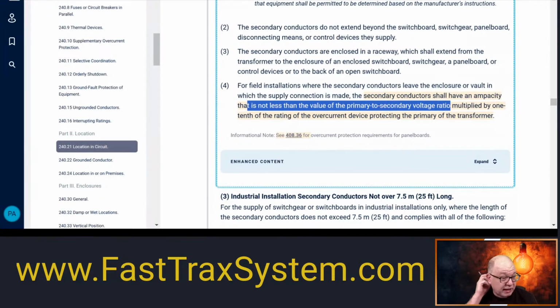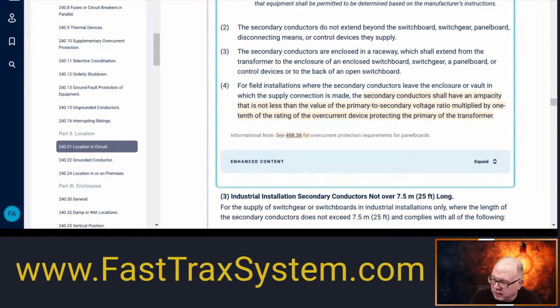And let's say, again, in our case, it was a 480 primary and a 208 secondary. So the voltage ratio would be 480 divided by 208, and that would be 2.307 or 2.31. So that's your ratio. All you did was divide the secondary into the primary to get this ratio. Okay, that's what it means. Then that ratio, multiply by 1/10 of the rating of the overcurrent device. So if it was a 200 amp overcurrent device, you divide that by 10, that is 20 amps.